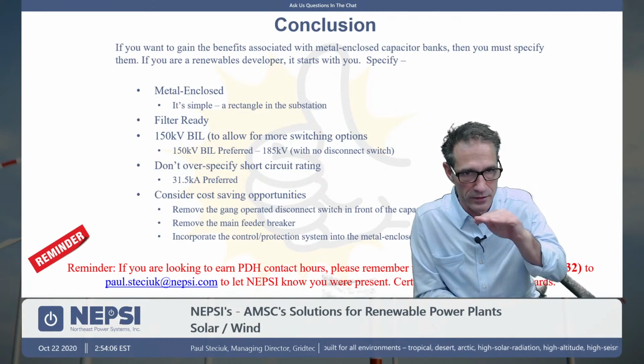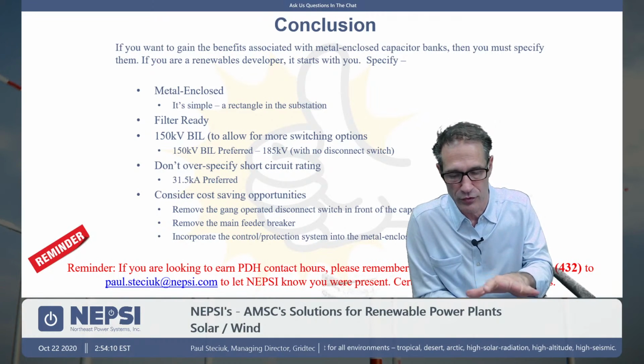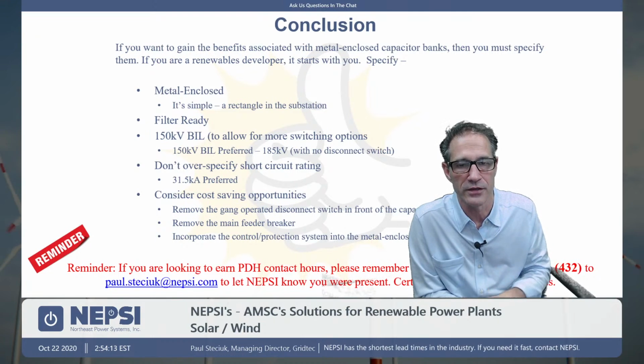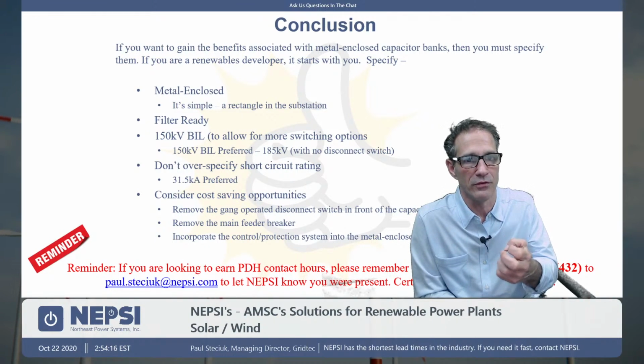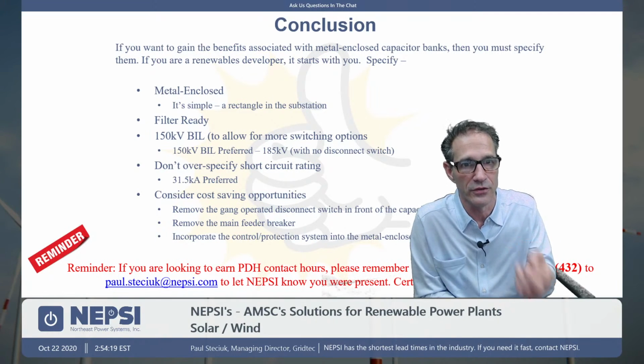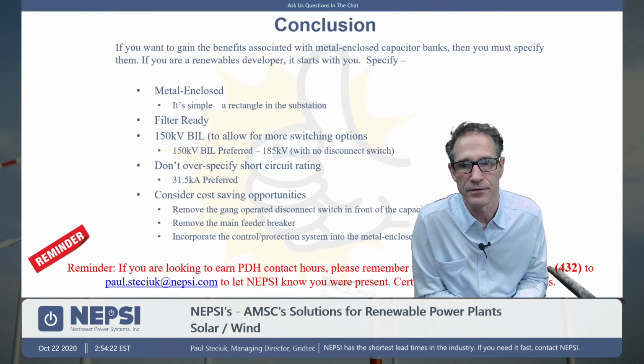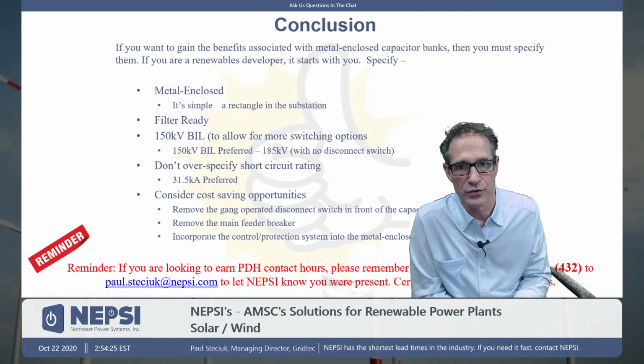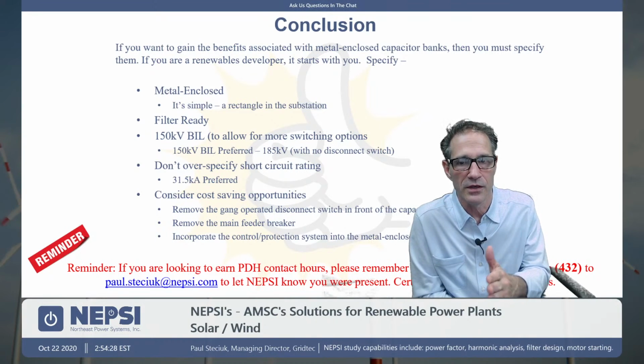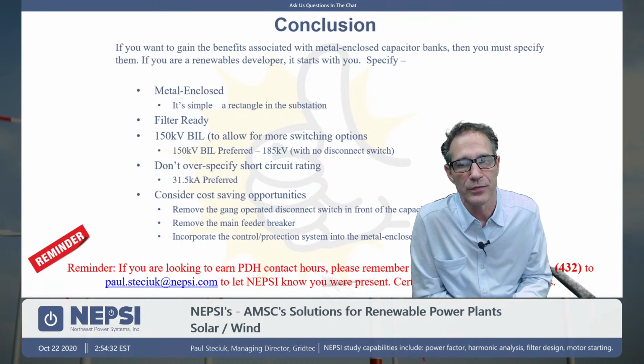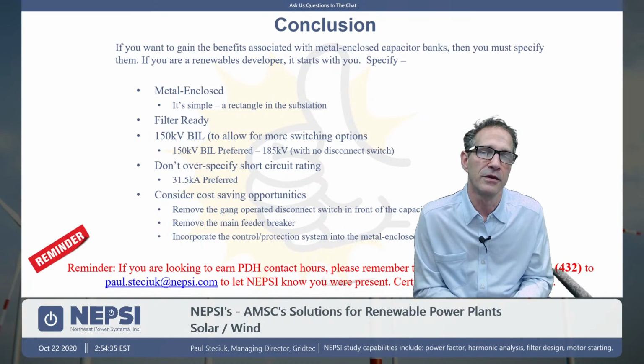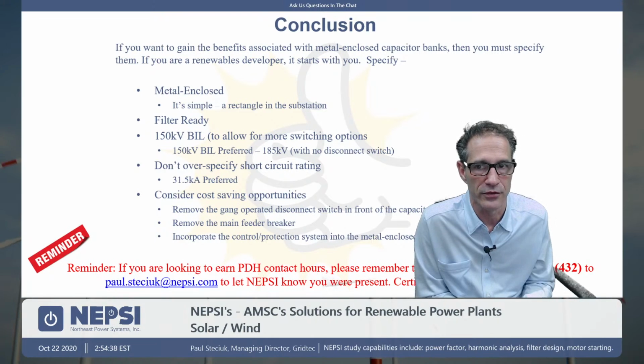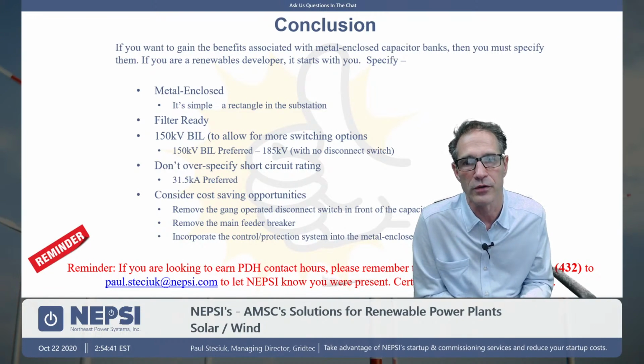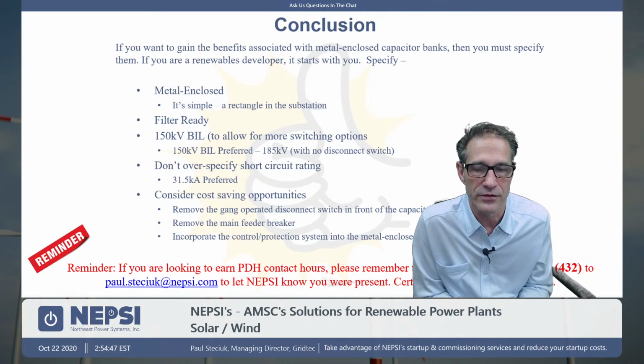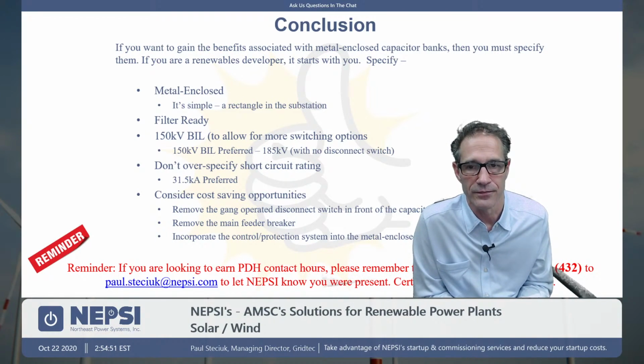If we need to go up, cap it at 185. 185 will allow us to use the VD4, VD4CS technology. We will just have to eliminate the disconnect switch. The disconnect switch that we use is 150 kV BIL. So don't overspecify the short circuit rating. Calculate the short circuit rating. If it's 31.5 kA or less, specify at 31.5 kA. They'll go straight to 40. And in so doing, we can use the VD4CS and the VD4, both of those switching devices, which are designed for capacitor switching. There will be a cost savings to you and a definite lead time savings to you.